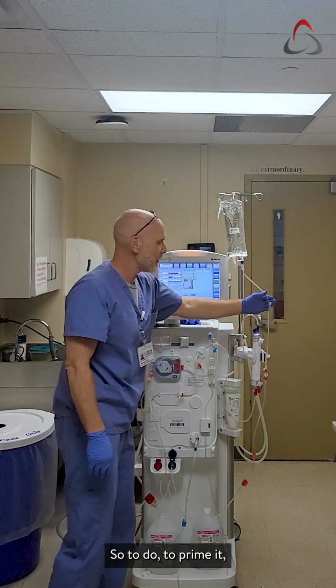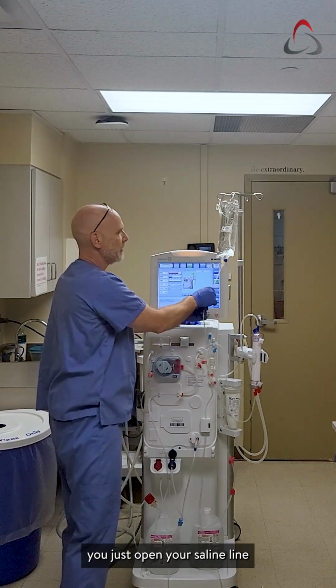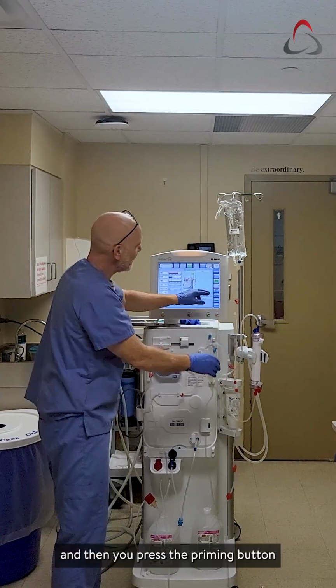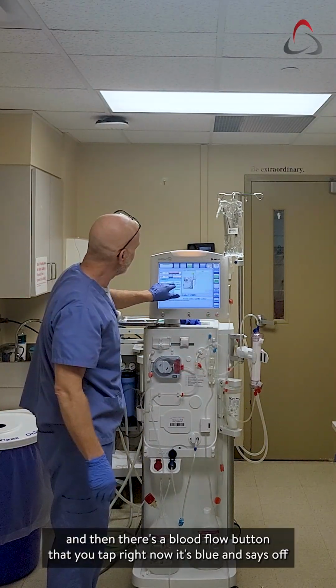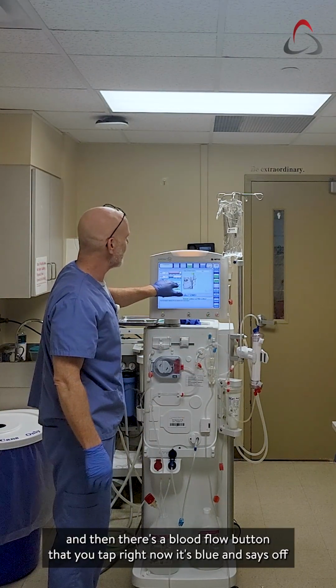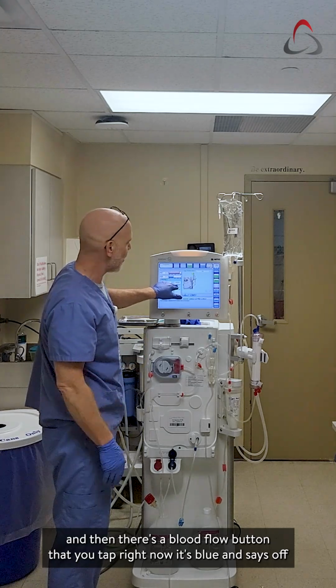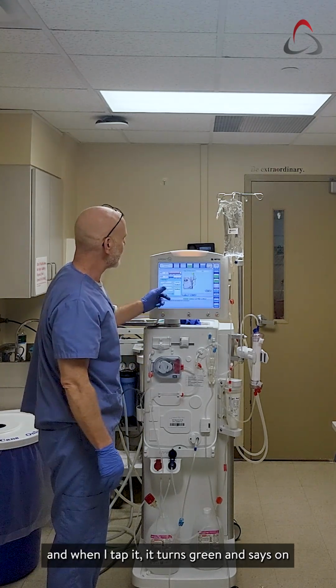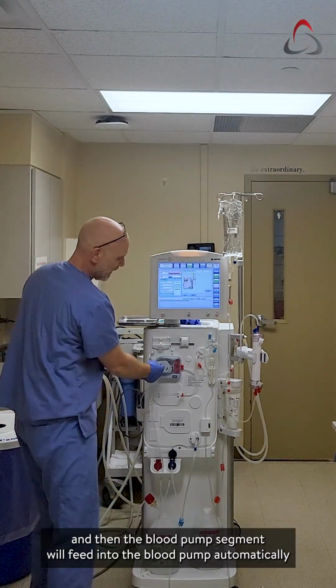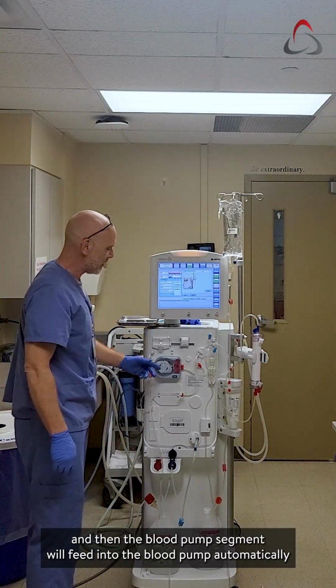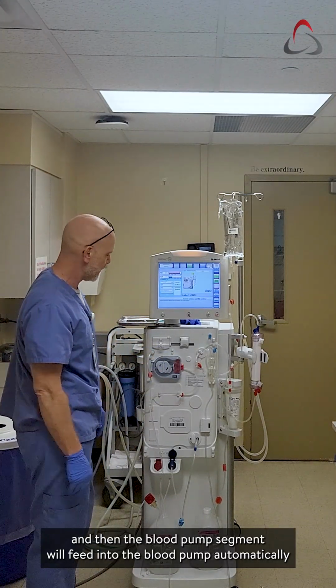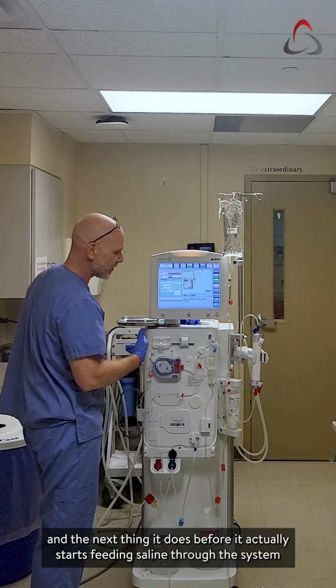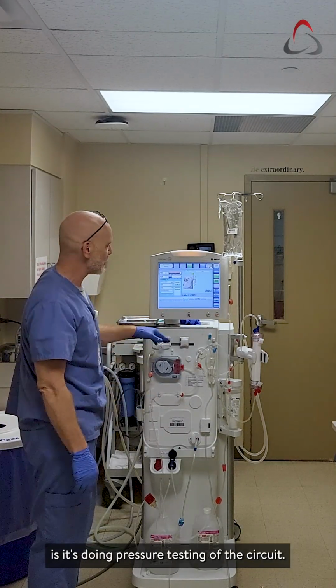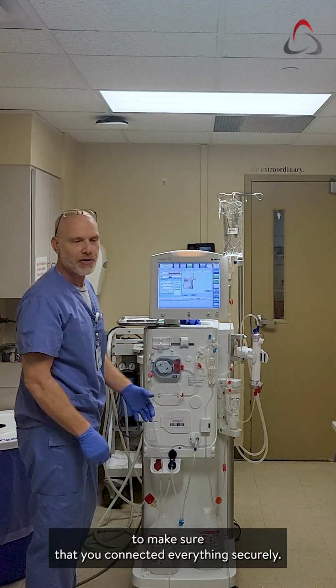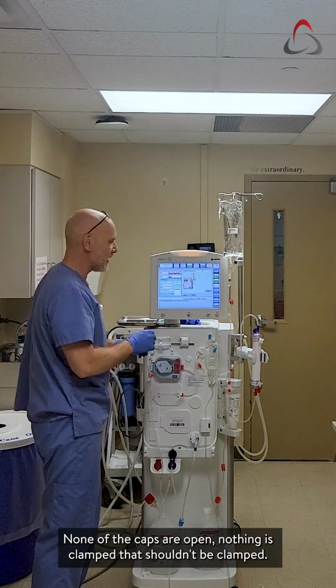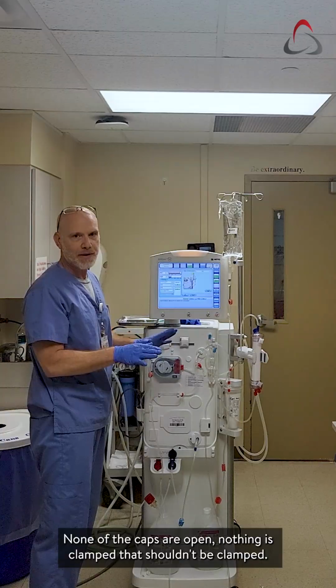So to prime it, you just open your saline line, and then you press the priming button, and then there's a blood flow button that you tap. Right now it's blue and says off, and when I tap it, it turns green and says on. And then the blood pump segment will feed into the blood pump automatically. And the next thing it does before it actually starts feeding saline through the system is pressure testing of the circuit to make sure that you connected everything securely. None of the caps are open. Nothing is clamped that shouldn't be clamped.